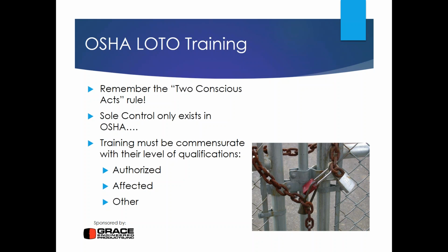So an authorized person is very highly trained, very well skilled. So every authorized employee is qualified, but not every qualified person is authorized. So keep in mind what that training requirement is, because the 70E requirements are a lot less clear than that. The term affected simply means what it says. It means some employees that are impacted by lockout tagout, but are themselves not allowed or trained to affix lockout tagout and control energy. An example of that would be a machine operator. If we lock out their machine, it certainly impacts their ability to function, but they actually are doing nothing with respect to energy control themselves.